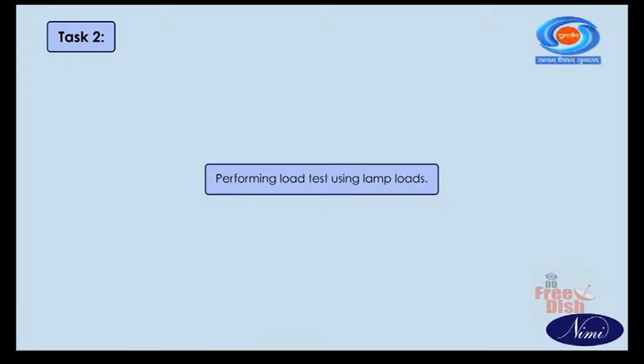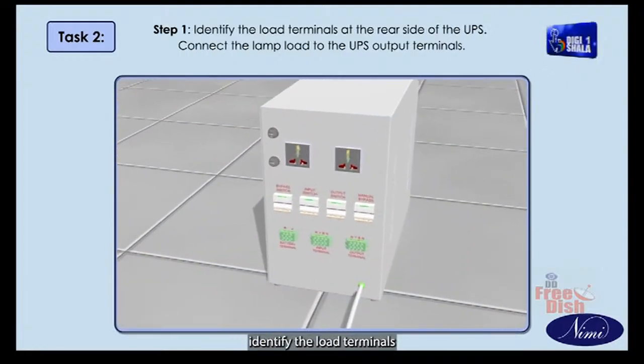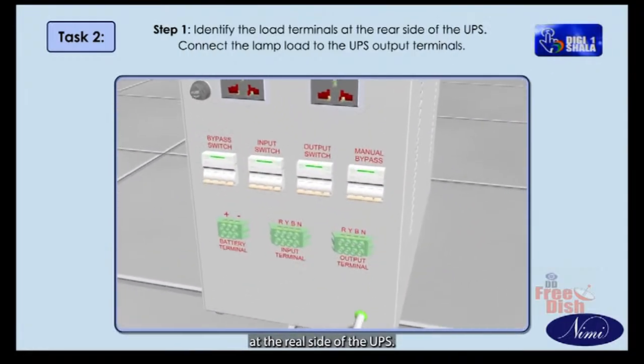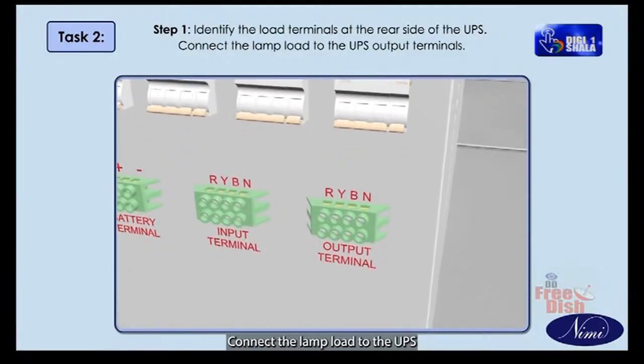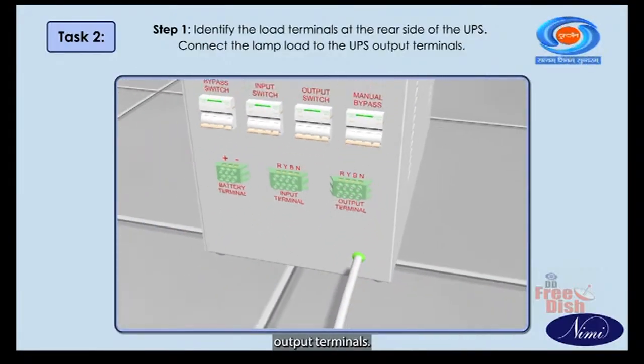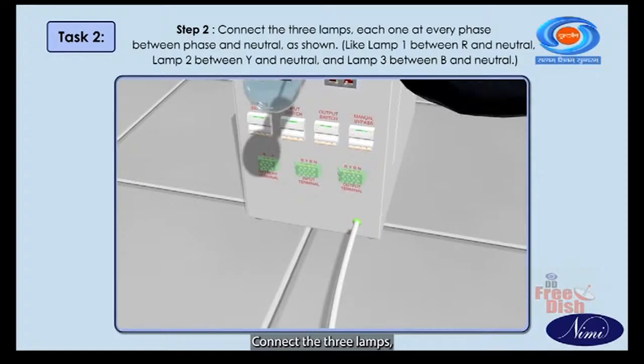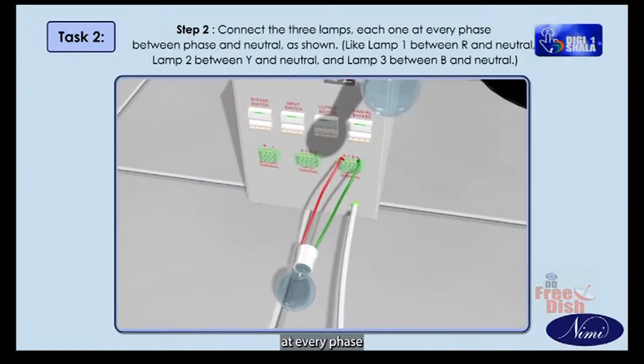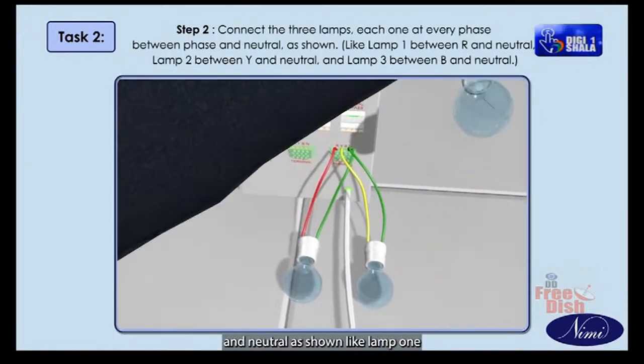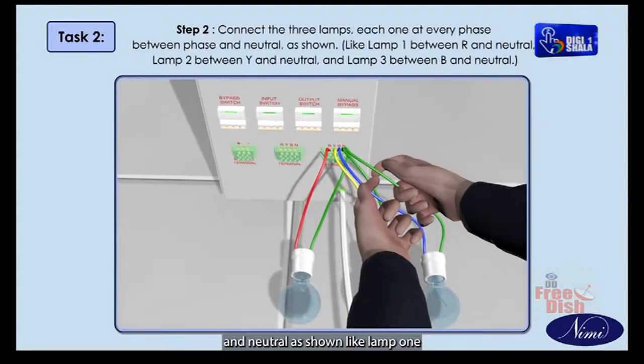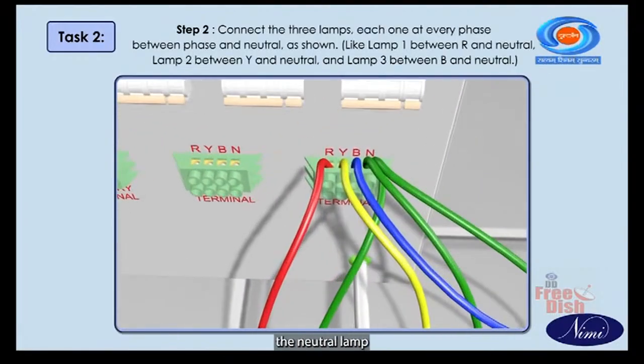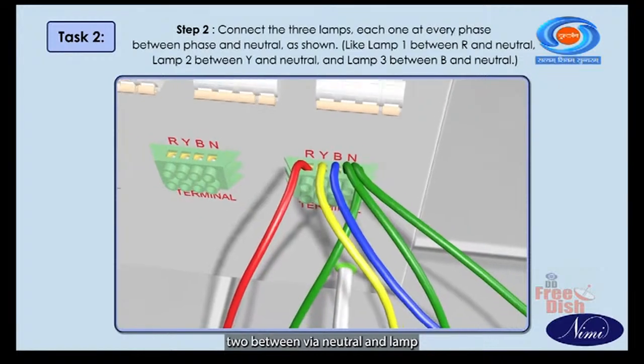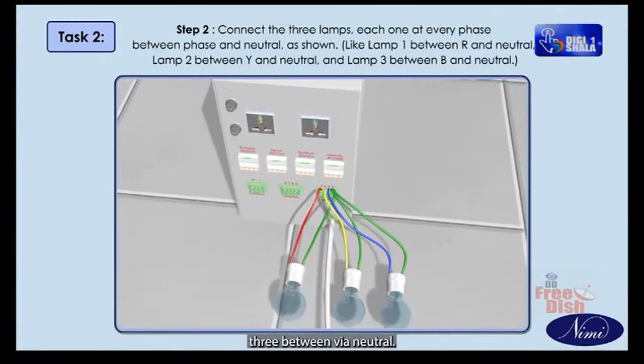Task 2. Performing load test using lamp loads. Step 1. Identify the load terminals at the rear side of the UPS. Connect the lamp load to the UPS output terminals. Step 2. Connect the three lamps, each one at every phase between phase and neutral as shown, like lamp 1 between R and neutral, lamp 2 between Y and neutral, and lamp 3 between B and neutral.